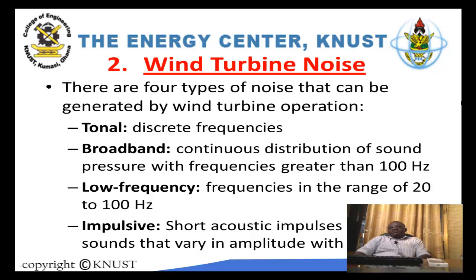Now we move on to wind turbine noise. As already explained in detail in the material, wind turbines actually produce noise, especially when working or moving at high speeds. The noise has been categorized into four types. You have tonal noise, where the noise is made of discrete frequencies. You have broadband noise, where you have a continuous distribution of sound pressure within or greater than a certain frequency range, which is about 100 hertz. Then there is low-frequency noise — sound within a certain range of about 20 to 100 hertz. And then there is impulsive sound, involving acoustic impulses that vary in amplitude with time. All these categories of wind turbine noise have been explained in detail in the material in very clear simple language.